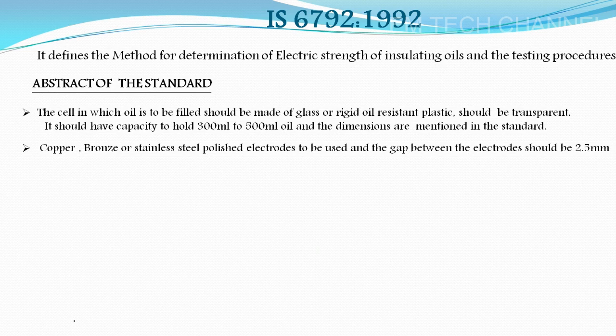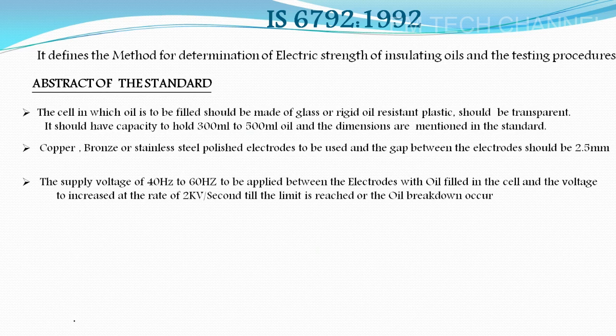Copper, bronze or stainless steel polished electrodes should be used, and the gap between the electrodes should be 2.5 mm. And the supply voltage of 40 Hz to 60 Hz should be applied between the electrodes with the oil filled in the cell, and the voltage to be increased at a rate of 2 kV per second till the limit is reached or till the breakdown occurs.